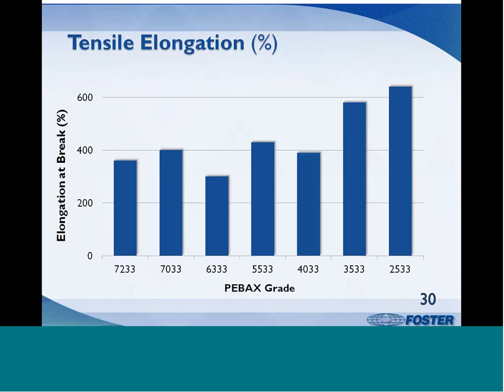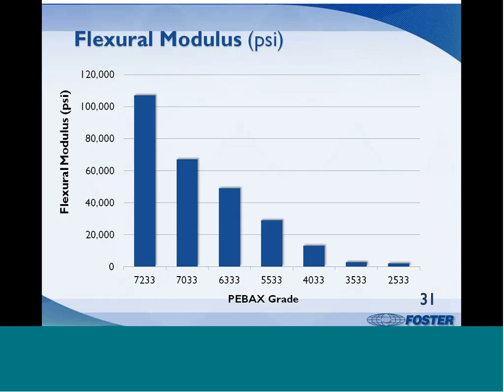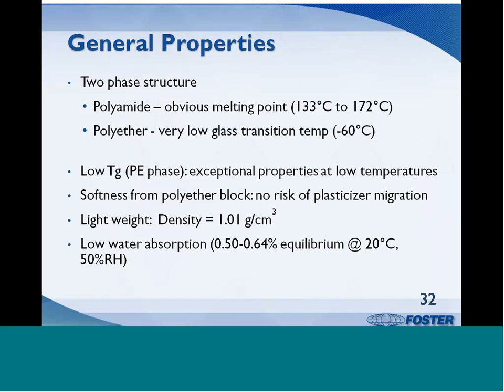Flexural modulus is very reflective of hard and soft block ratios. The hardest grades would be best for transferring torque, while the soft grades are appropriate for catheter tips, where it needs to softly sneak around corners without causing tissue damage. The key to a good block copolymer is having two components that are compatible, but that phase separate to build a self-reinforcing morphology. In this way, the best of the hard and soft blocks can be taken advantage of. Pebax maintains its low temperature flexibility better than competitive materials, as shown in this graph. TPU and polyester elastomers become significantly harder as the temperature drops below 0 C.